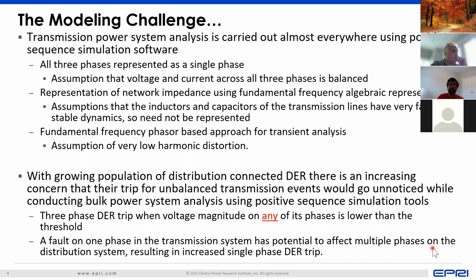But even though a single-phase fault is more common, DER on multiple phases, and this could be single-phase DER, can now get impacted because of a single-phase fault, which further leads to the imbalance and further leads to the transient. So there is a lot of approximation that we have to do based upon engineering judgment in order to consider these various factors while representing them in something called a positive sequence analysis.